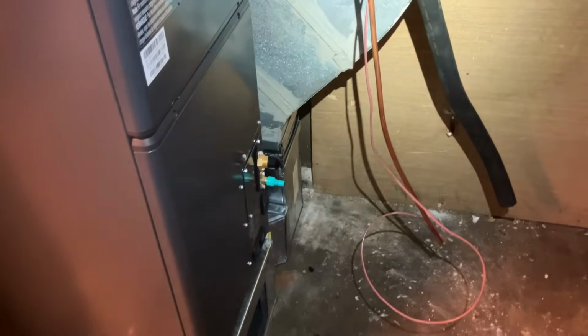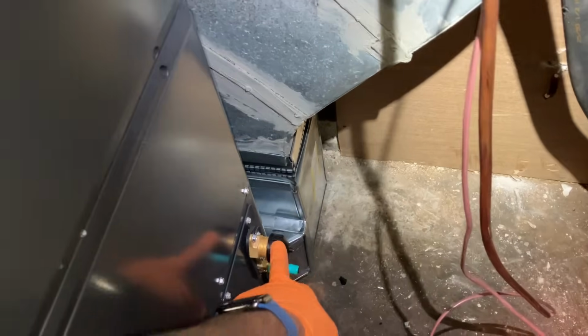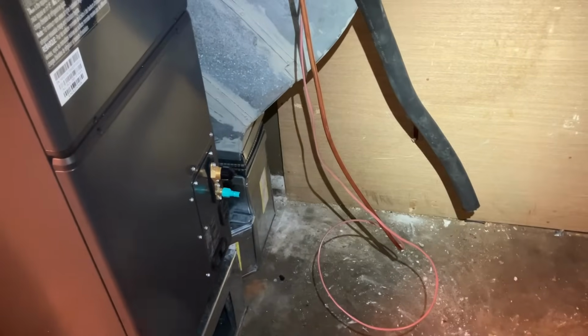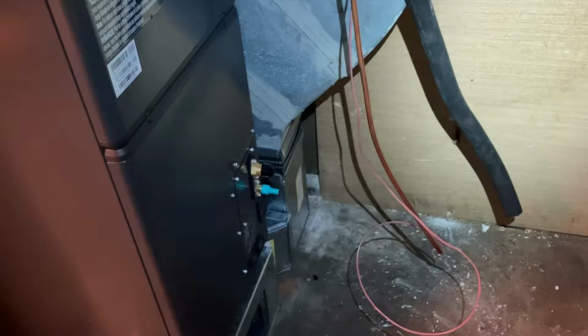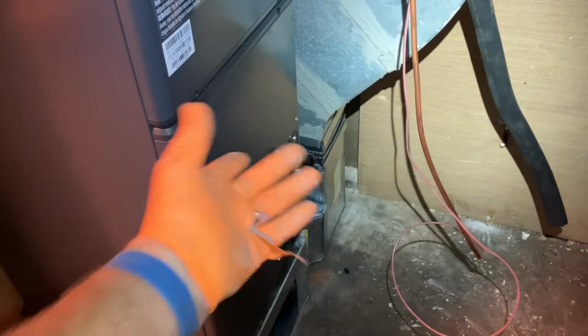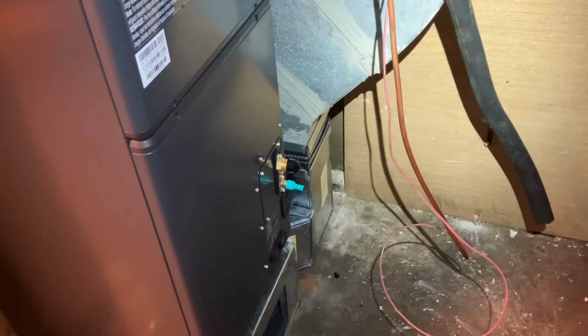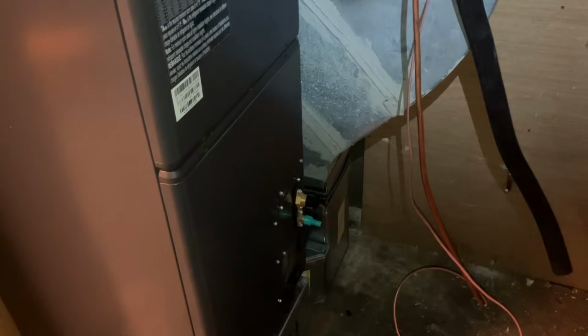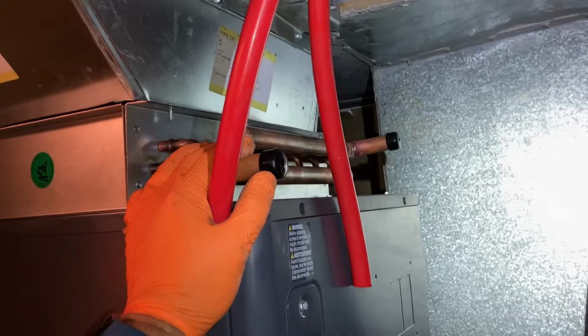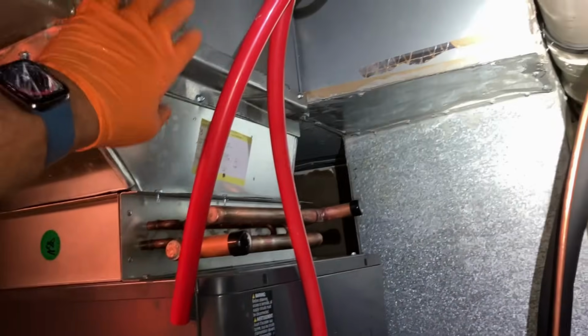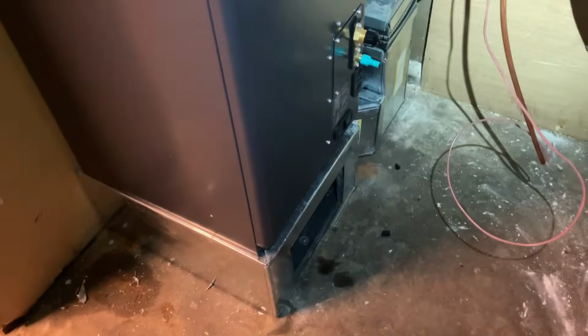All right, I got my line set ran to this air handler, all the way out there. I'm gonna have to throw a couple couplings outside on the 3/4 and the 3/8, but we're gonna use the supplied flexible adapters with flare on one side that allow us to braze, or we can cut the swedge off and ZoomLock onto the flexible adapter. I'll show you that in a minute outside when we start working on the line set connections, but we still got to do the hydronic coil here, and tape up and mastic the seams, but it's looking pretty nice.